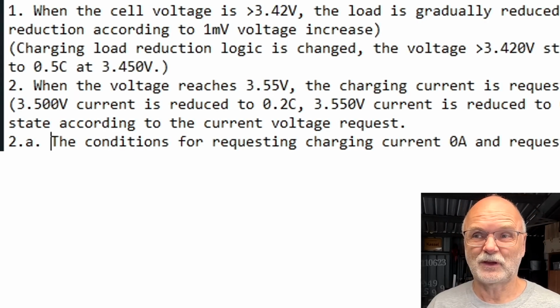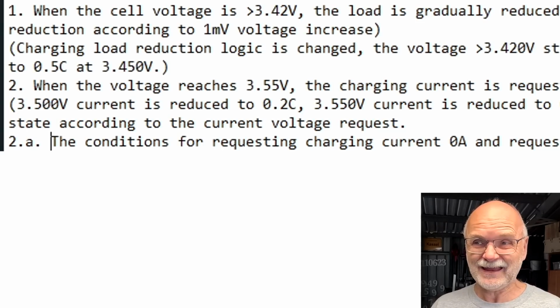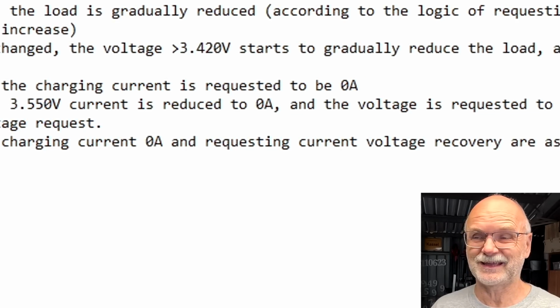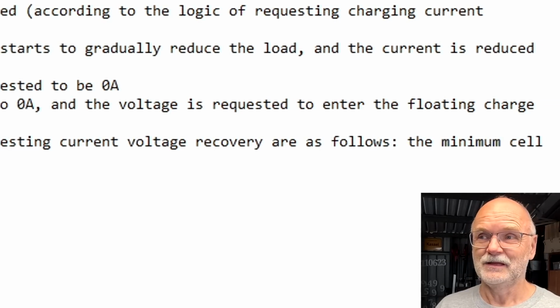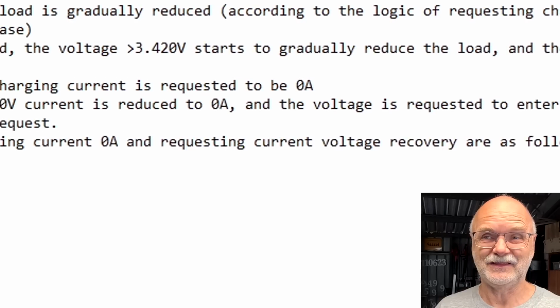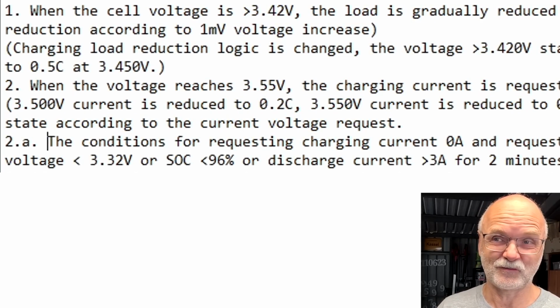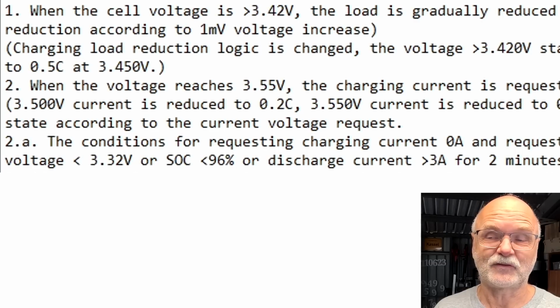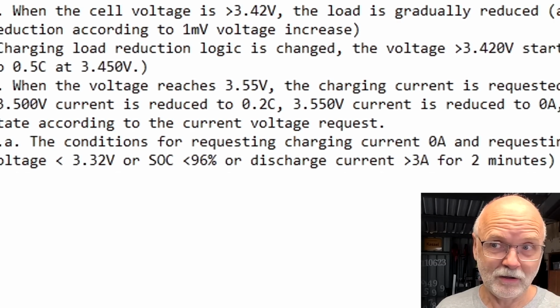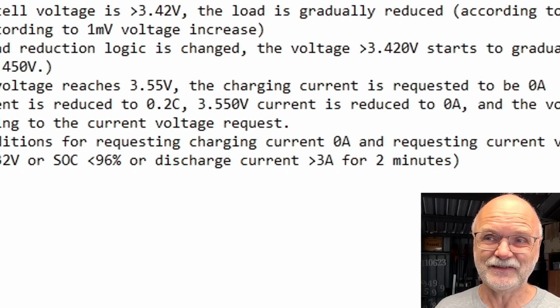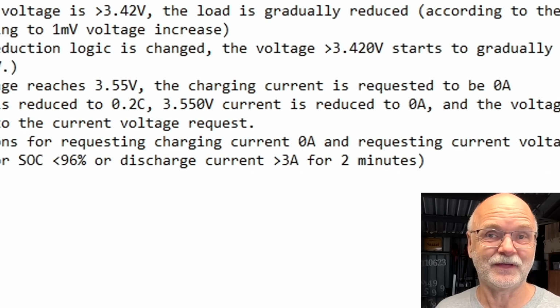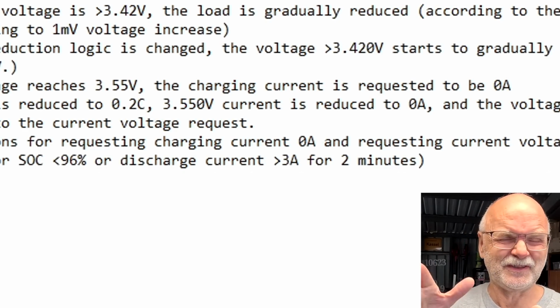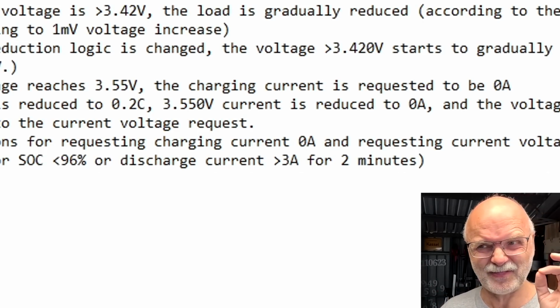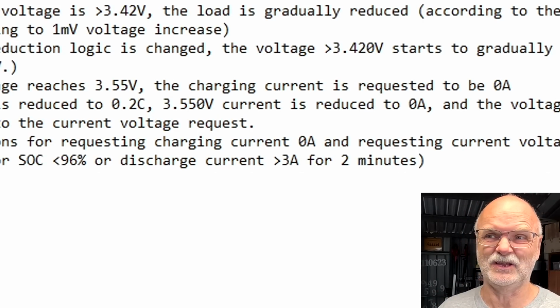The conditions for requesting charge current 0 and requesting charge current voltage recovery are as follows: the minimum cell voltage is smaller than 3.32 volts, or state of charge is lower than 96%, or third possibility, the discharge current is higher than 3 amps for 2 minutes continuously. So this point is a bit weirdly translated, but I think this is the rebulk situation they're describing here.